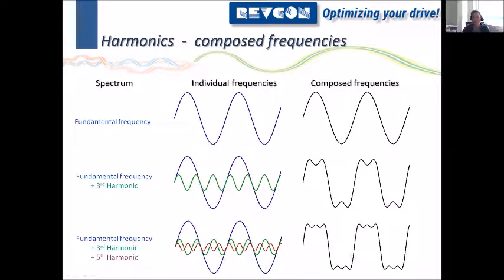Okay, but first of all, we need to understand what a harmonic is. When we have AC current, we expect a sinusoidal current, of course. But in fact, the truth is typically different. We can look at any current waveform and decompose this signal into individual frequencies. Sometimes it's easier to understand if we look at it the other way around. Looking at the picture in the middle, we have the fundamental frequency and the third harmonic. The third harmonic is just 3 times the frequency of the fundamental frequency. So far, so simple. If we add up these frequencies, we get a composed signal. This is what we get when we add up fundamental and third harmonic. If we add up the third harmonic and the fifth harmonic, we get something looking like this.